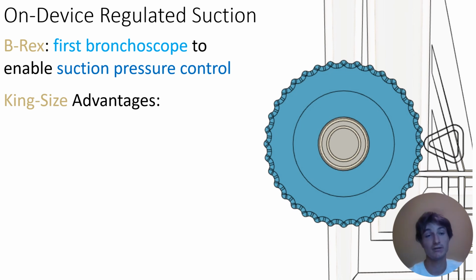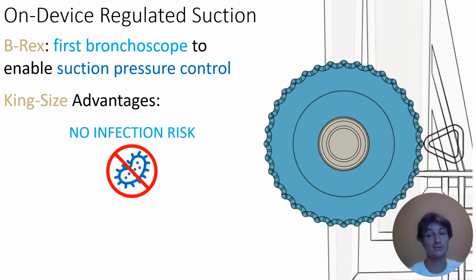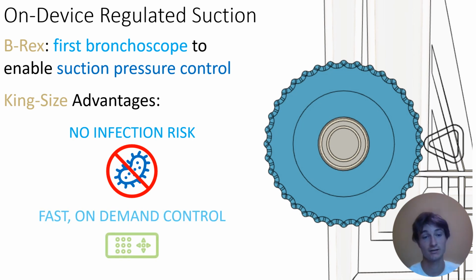In addition, since the B-Rex has its built-in regulator and offers suction pressure control, there's no infection risk from a wall regulator because you don't need to connect to one. Additionally, with it being right there on the device, it saves time and saves the number of steps in the procedure, because no longer do you have to go over to the wall to change the pressure during the procedure. This happens quite a lot during procedures because as you go into a more peripheral airway, there's less cartilage structure, so it's easier to collapse. So you really need to lower the suction pressure as you go into smaller bronchi.